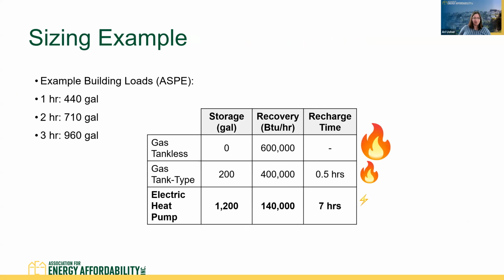Just a quick sizing example for the same building with gas tankless, gas tank type, or electric heat pump. You're seeing that to provide the full demanded hot water, the storage is going to need to be bigger for heat pumps. This is really to accommodate that longer recovery time. Storage is going to need to be sized to provide the full hot water needed to cover our peaks, and that's a little different than traditional gas systems.